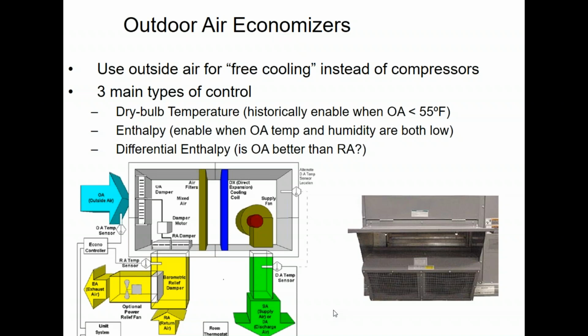We can also look at enthalpy. Enthalpy allows us to look at both temperature and humidity simultaneously, if you will. So if the outside air temperature is low and the humidity is also low, we can go ahead and use the economizer to get free cooling. That allows us to push the set point for temperature up a little bit higher, right? I'll take 60-degree air if it's dry, but if it's 60 and raining, I probably don't want it.